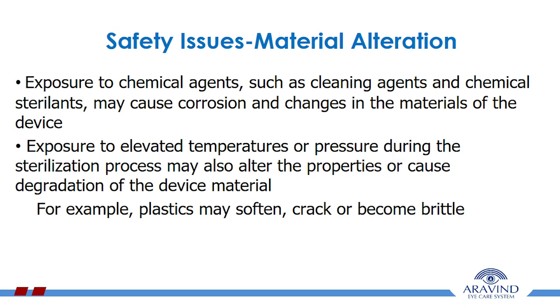Also, exposure to chemical agents such as cleaning agents and chemical sterilants may cause corrosion and changes in the materials of the device. Exposure to elevated temperatures or pressure during the sterilization process may also alter the properties or cause degradation of the device material. For example, plastics may soften, crack or become brittle.